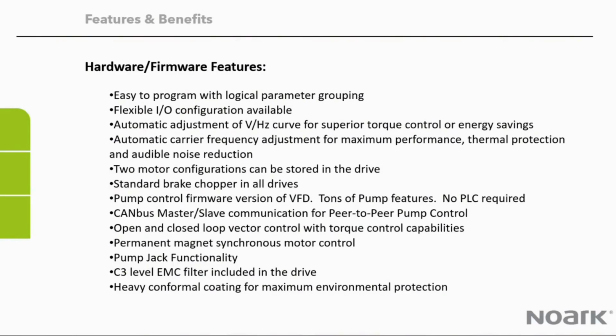Flexible I/O, we can configure it to numerous different conditions that'll help for your application. There's an automatic adjustment of the volts per hertz curve to provide better torque or energy savings. The one that I've seen a lot of recently is the automatic carrier frequency. A lot of manufacturers don't have that. And that gives you better performance.